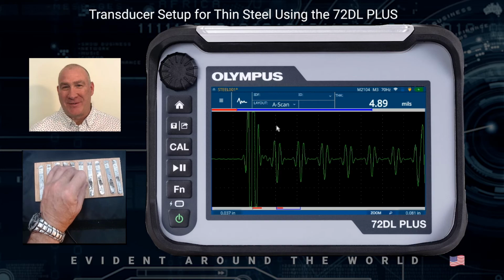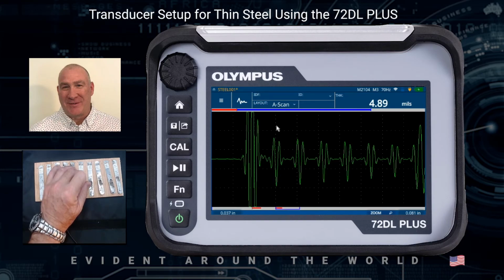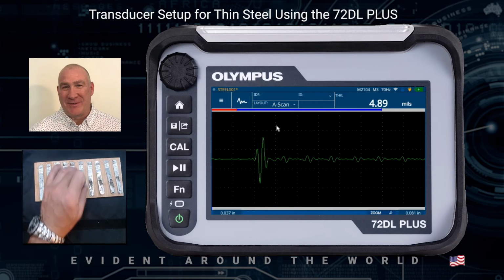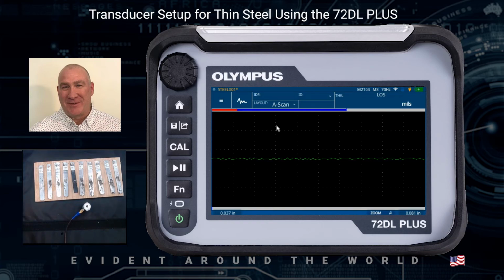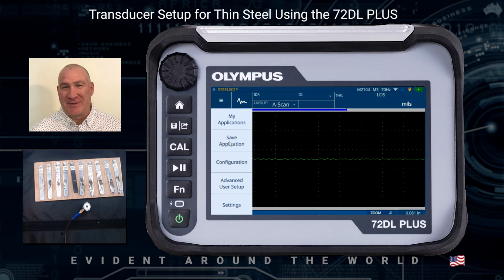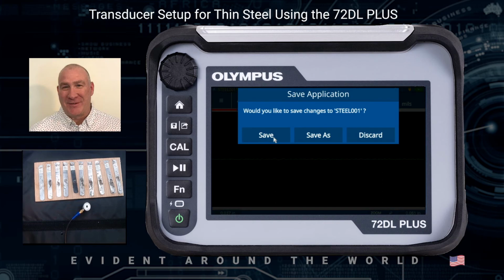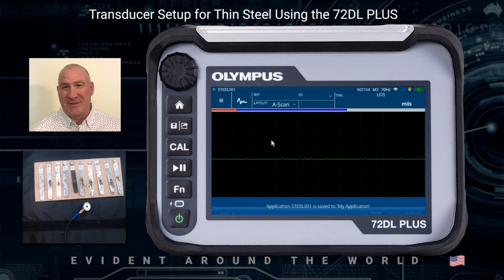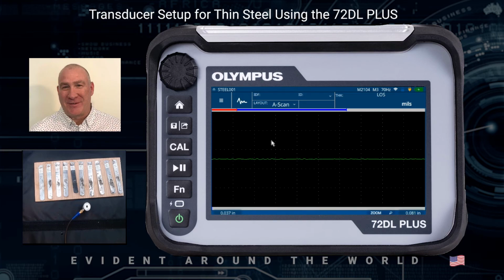Now I could go ahead and do a calibration, cal velocity, cal zero. That's going to be demonstrated in a different video. At this point, I'm all set. Looks like I'm getting good detection. I can now go in and save my setup. I click on the burger menu, then click on Save Application. I can hit Save, and this will save any of the changes that I made along the way. This concludes the video on how to set up the M2104 125 megahertz high frequency transducer on thin steel in a mode 3 measurement. Thank you.